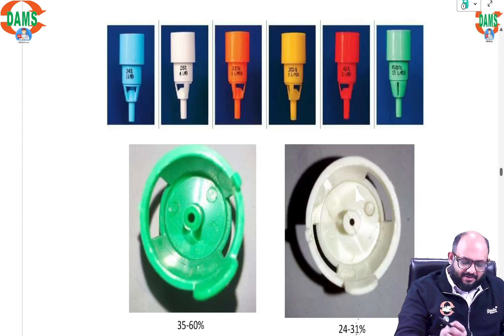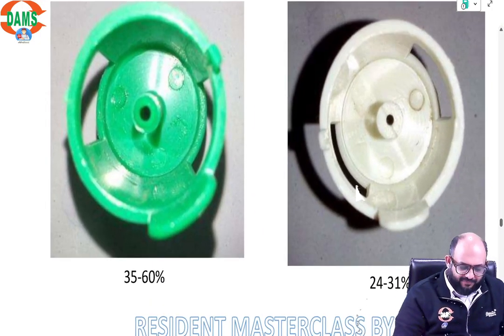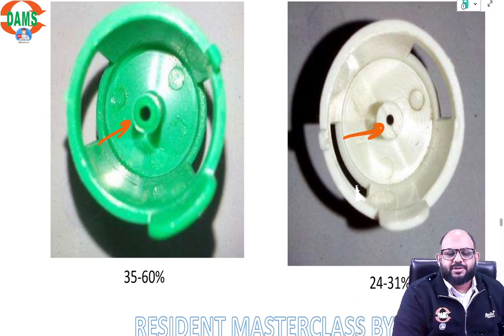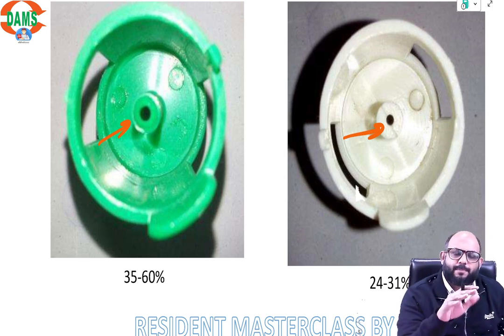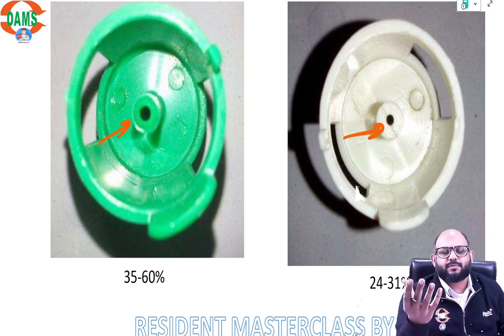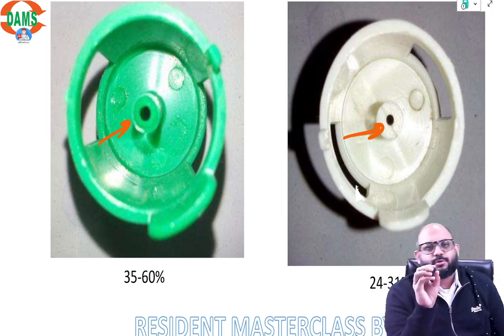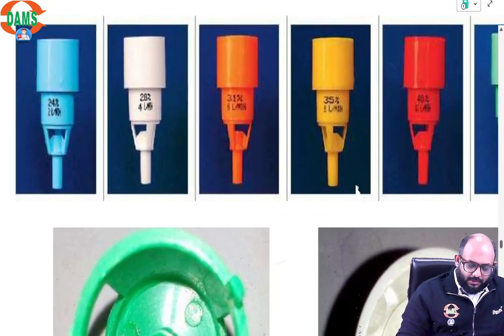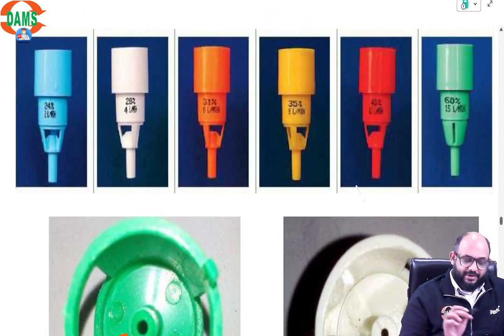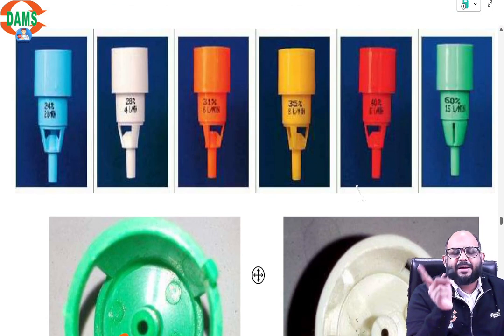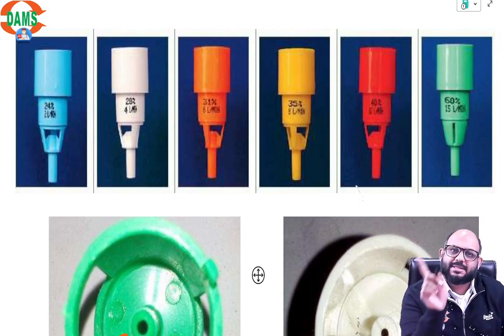So when you see a Venturi valve, different Venturi valves will have different calibrations or calibers or openings. The smaller the caliber, the faster the flow rate, the more drop in the pressure, the more entrainment of the gases, the lesser the FiO2. So for every FiO2 that you need, there will be a different valve, and every valve should have a different flow of oxygen that you keep.